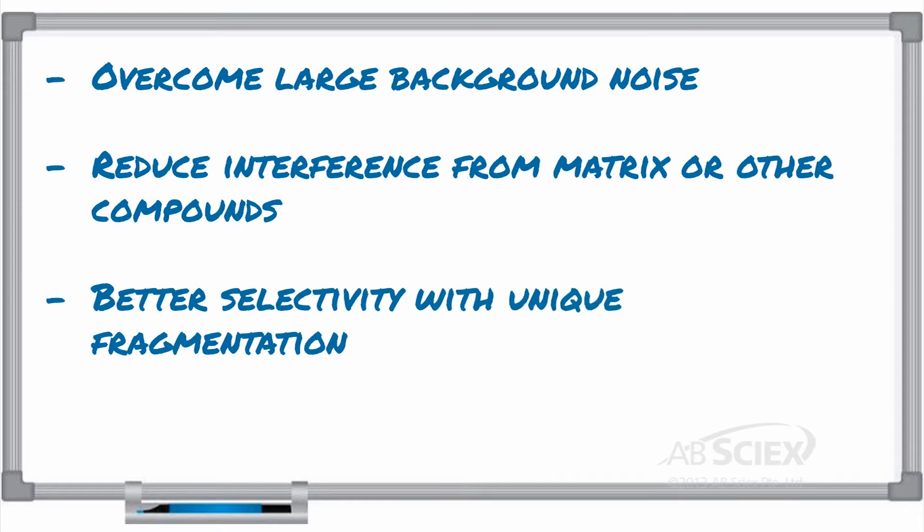We've told you a little about the benefits of MRM-cubed: the ability to overcome background noise in your chromatogram, the reduction of matrix interferences in your MRM transitions that interfere with your quantitation, and the ability to improve the selectivity for detecting your compound of interest.